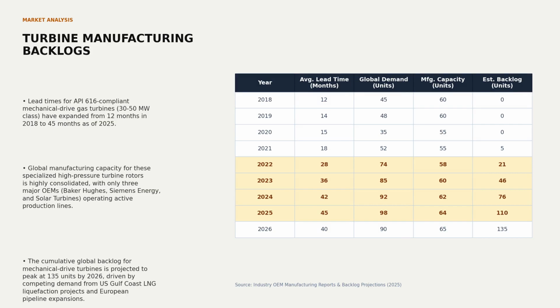Lead times for 30 to 50 megawatt mechanical drive turbines have expanded from 12 months in 2018 to 45 months in 2025. Only 3 original equipment manufacturers globally possess the capability to produce these specialized high-pressure rotors. This consolidation leaves pipeline operators competing directly with global liquefied natural gas export terminals for manufacturing slots. The cumulative backlog is projected to peak at 135 units by 2026.